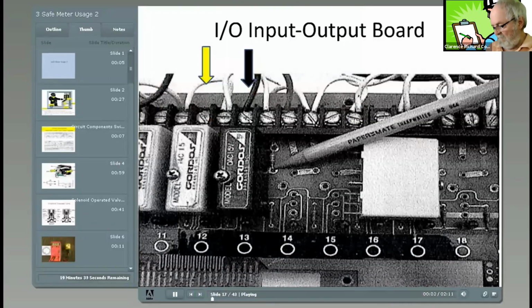Analog input and output boards are where the rubber meets the road when it comes to computers and wiring to the plant. When the computer tells the plant to do something, an LED lights up the output for that task to be performed. The signal is sent to a solid-state, black relay, and power is sent to a starter or solenoid, etc. The computer listens to the plant when gates are all the way closed, or an asphalt meter or belt scale is reporting its status and rate through yellow, white, red, etc.